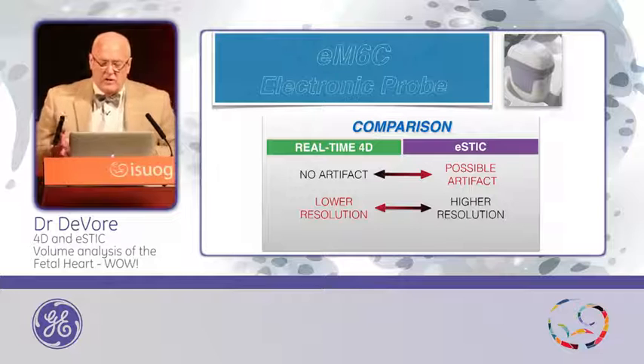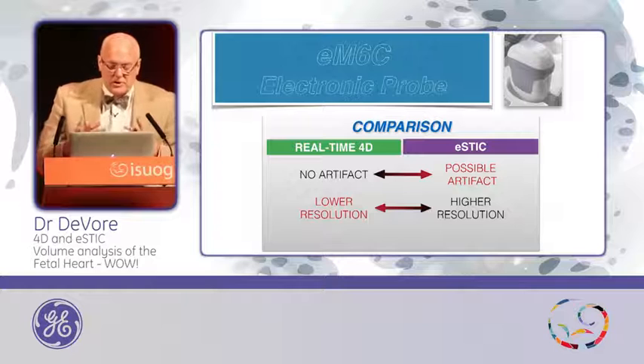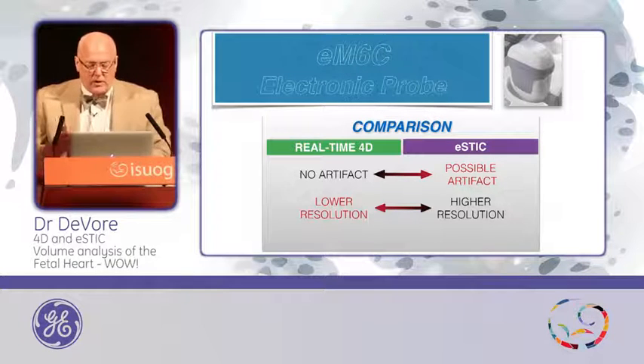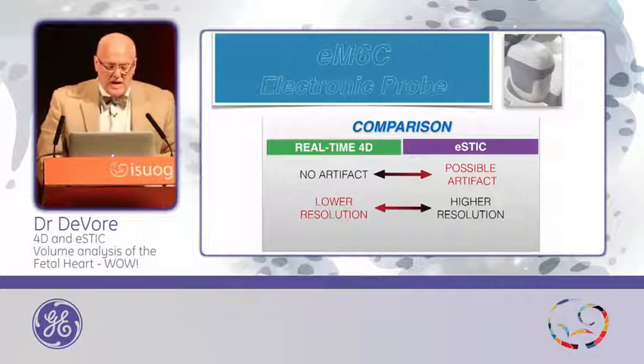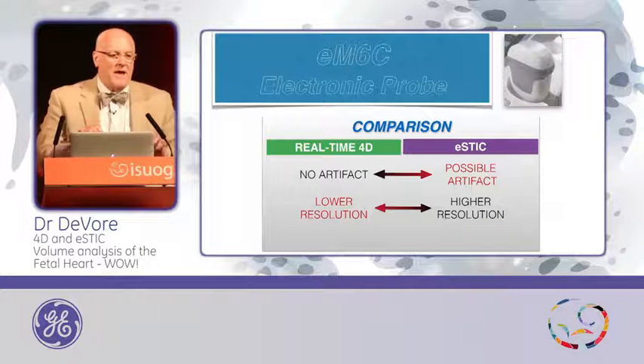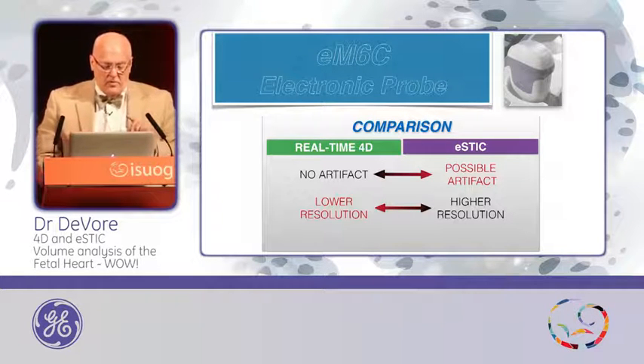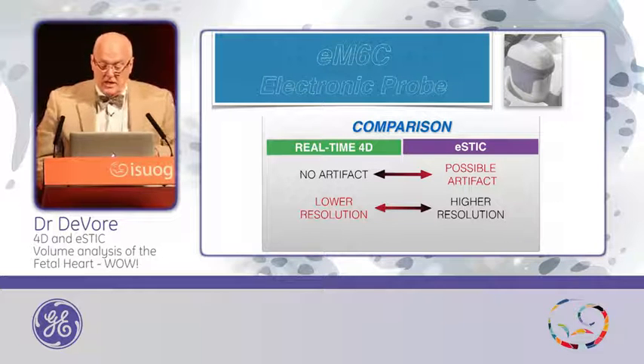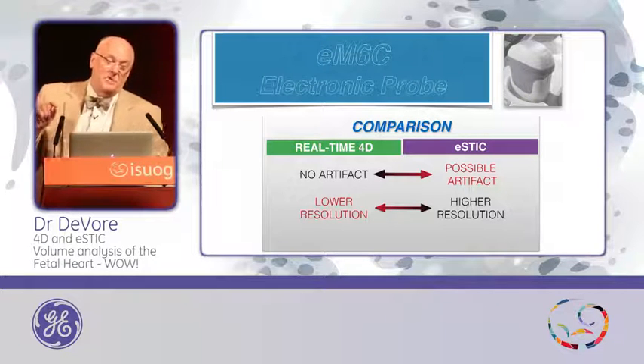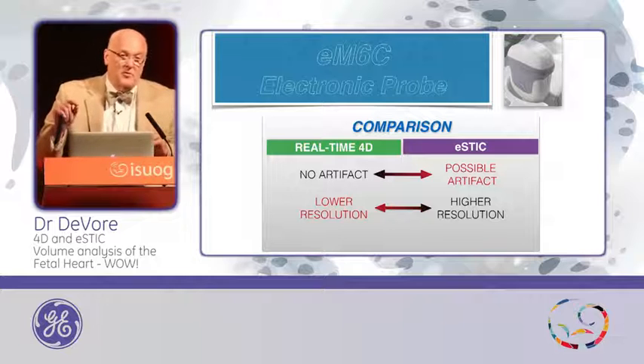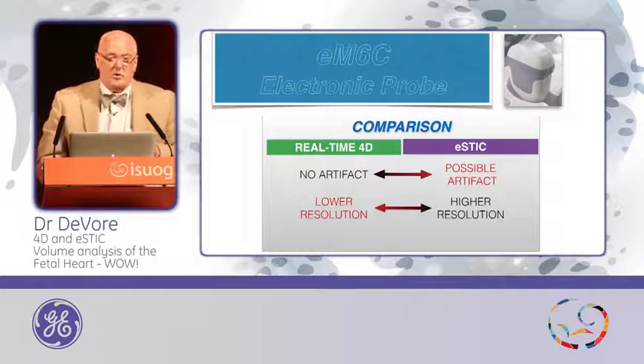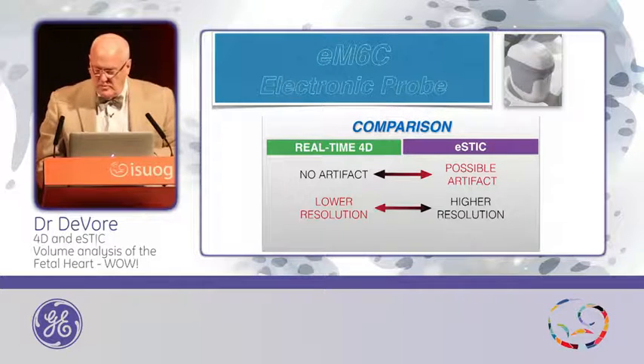If we drill down on the drawbacks and benefits of each approach — real-time 4D or eSTIC — real-time has no artifact in the B and C planes, period. You don't see artifact because it acquires so fast it creates a single volume. However, the resolution is a little bit lower than the eSTIC. The eSTIC has a potential for artifact, but because it sweeps so fast, you rarely see it, and it has the ability for higher resolution along with other properties we'll see in a moment.